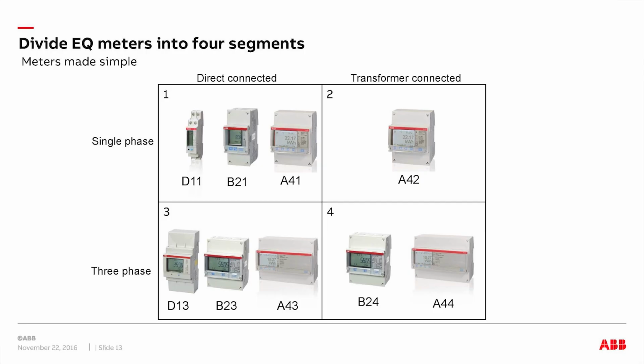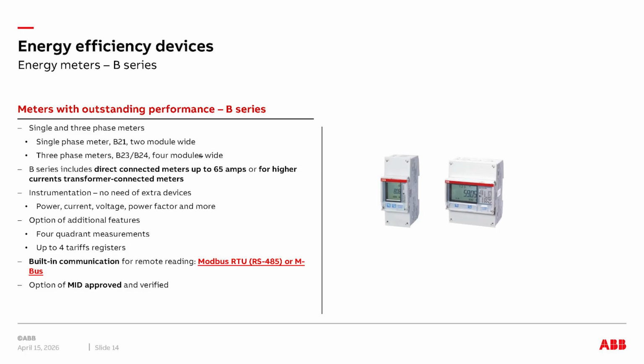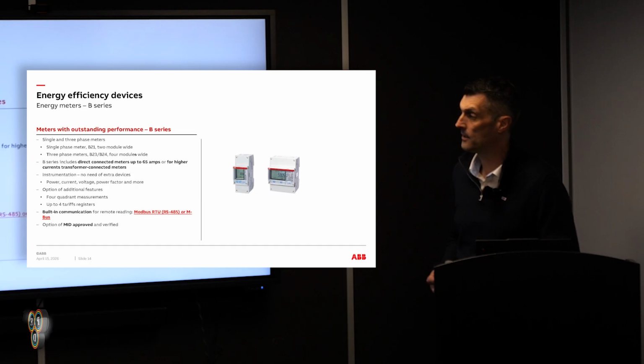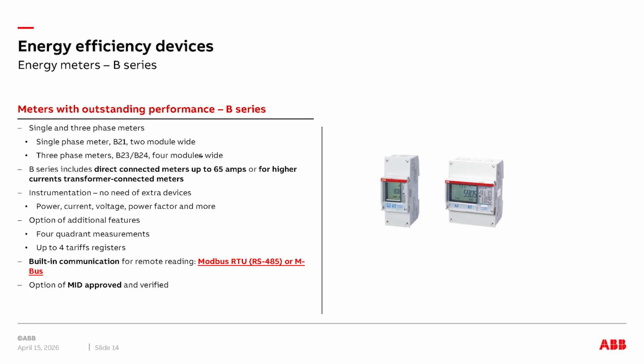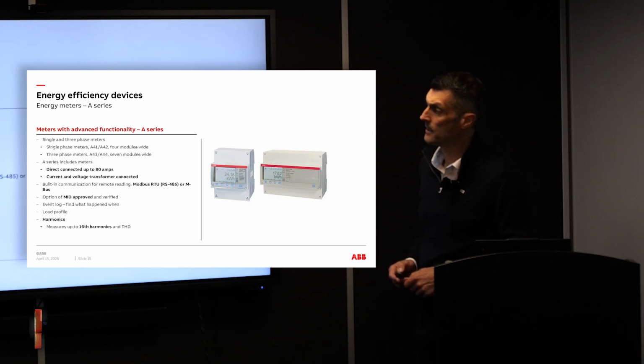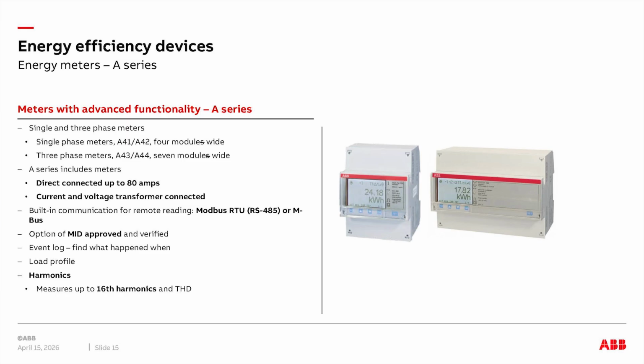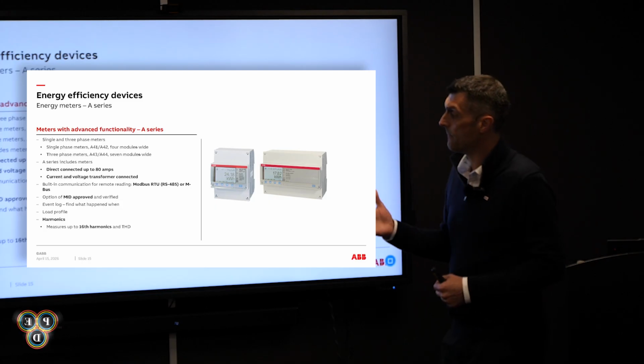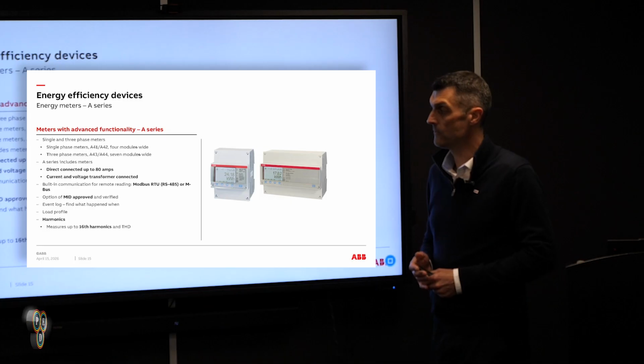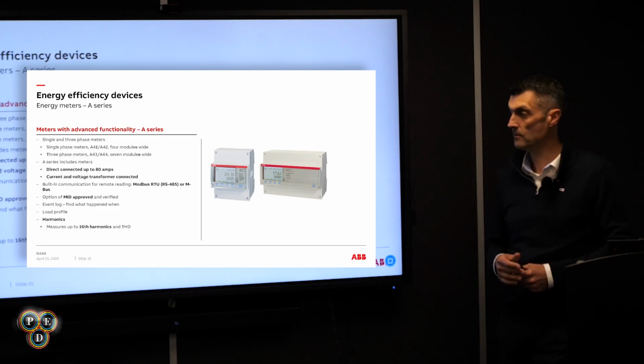Traditionally these were simple kilowatt hour meters, but they've become a lot more advanced over time. The B series features direct connected meters up to 65 amps, and above that you'd use a CT, or current transformer, for higher ratings. These can talk Modbus RTU for integration with BMS and EMS, and there's also an MID approved version for billing. The A series comes in direct connected up to 80 amps, slightly higher, with CTs above that, Modbus RTU integration and/or MBus, and an MID approved version for billing as well.